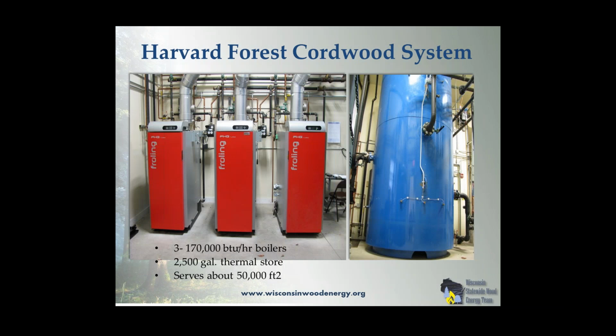This is a cordwood system. This is at Harvard Forest. It's Harvard's research forest that is about an hour and a half west of the university in Cambridge. It took a little bit to get there, but as of a couple weeks ago, they were able to supply about 90% of their heating load from these 3 boilers to 5 buildings, I believe, that are connected. Maximum capacity here is about 500,000 BTUs an hour for the 3 units.